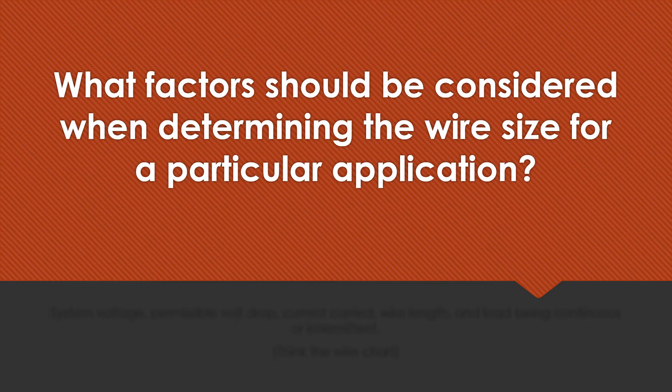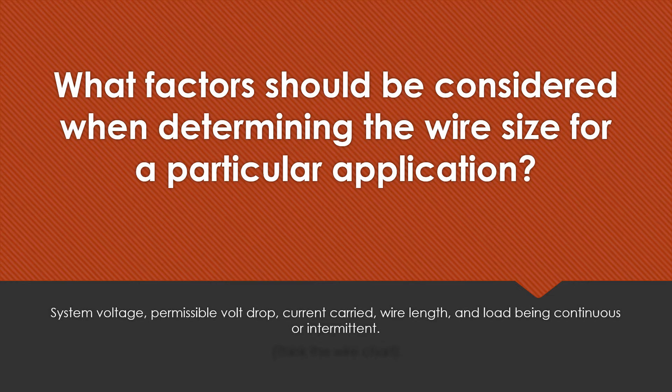What factors should be considered when determining the wire size for a particular application? System voltage, permissible volt drop, the current being carried, the wire length, and whether the load is continuous or intermittent are all important. Remember to think about your wire chart.